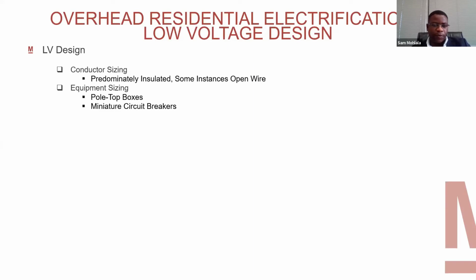Miniature circuit breakers are the breakers you put on the protective structures to protect your customer service cables. For these breakers, you also have to take into account the type of curve used. Using discrimination for the system, the circuit breaker we put on the pole top box is normally the orange toggle, which in terms of curves is curve 1 - meaning this breaker will trip second, or last, before the breaker inside the customer's unit.